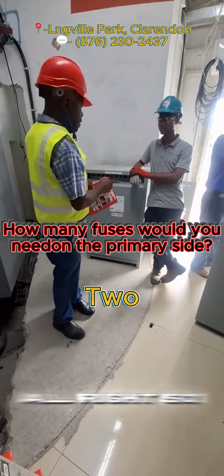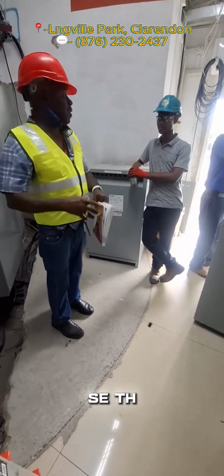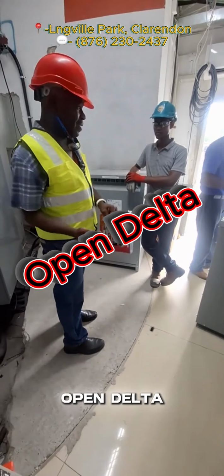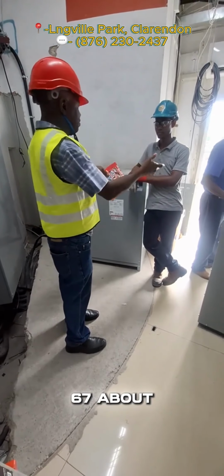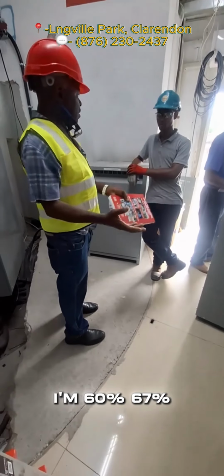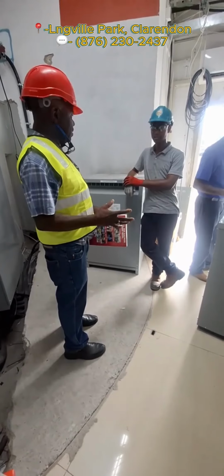So you say I can get a three-phase supply from those two transformers - in that case, that would be an open delta. And with an open delta, you'd actually get about 67% of the closed delta.